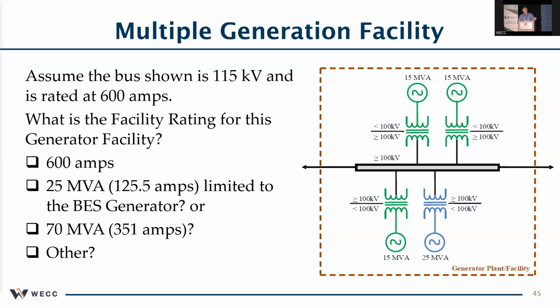But if you look and say 600 amps, yep, that's the most electricity you could ever see in that bus ever going out to the transmission owner. But realistically, you're never going to see more than 70 MVA because that's the total of all that generation there. Never going to get any more than that. And then if you look at BES, some people might say, well, I'm not talking about the BES generator. That BES generator is just that 25 MVA generator down there. So really the best answer is probably other, need more information.